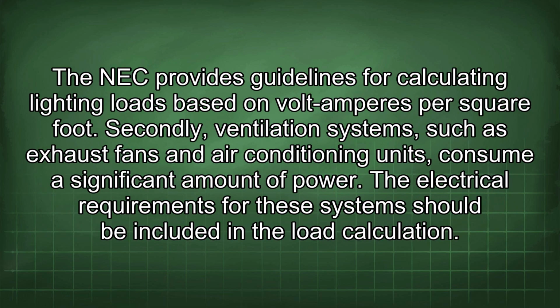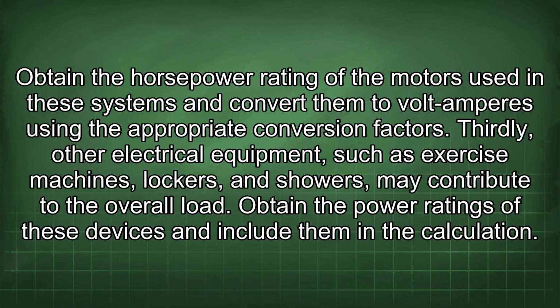The NEC provides guidelines for calculating lighting loads based on volt-amperes per square foot. Secondly, ventilation systems, such as exhaust fans and air conditioning units, consume a significant amount of power. The electrical requirements for these systems should be included in the load calculation. Obtain the horsepower rating of the motors used in these systems and convert them to volt-amperes using the appropriate conversion factors. Thirdly, other electrical equipment, such as exercise machines, lockers, and showers, may contribute to the overall load.